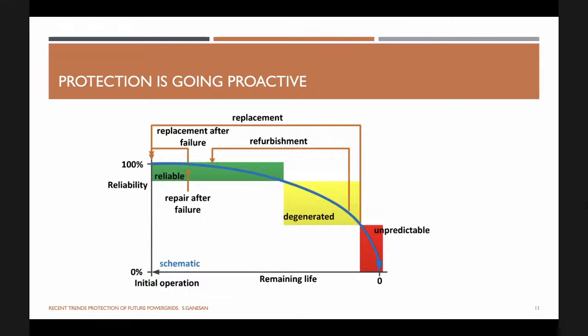We have so much information available in hand that you are able to do very big data analytics, and you are able to say where a particular equipment is heading with respect to its reliability. Typically, for a transformer you would do possibly a dissolved gas analysis, maybe once a year or once in a few months. You may tap something and then take the data manually. You would analyze—oh yeah, okay, this level is lower than expected, and I can possibly do something about it. So that's a typical thing.